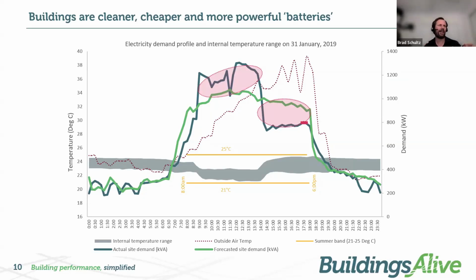You might go 23.5, 24 degrees because it's hot outside, and people are still going to be comfortable at that temperature. But what we do is essentially lower it early in the day, and then just before 2pm, when the peak demand charges kick in, just drop them back. There's a lot of other strategies that can be done as well.